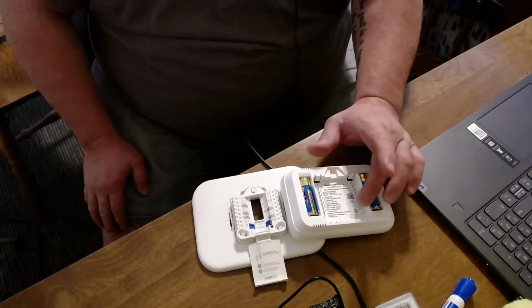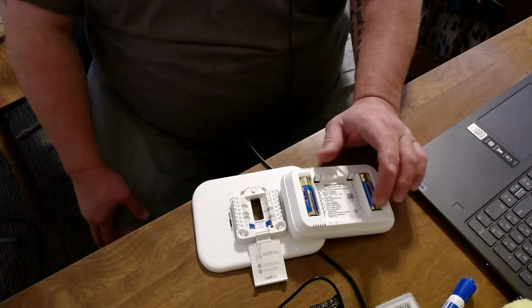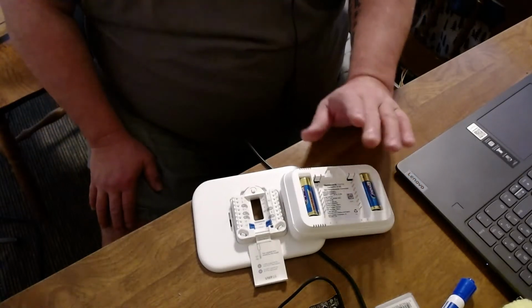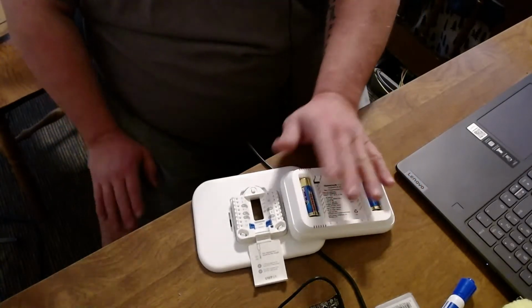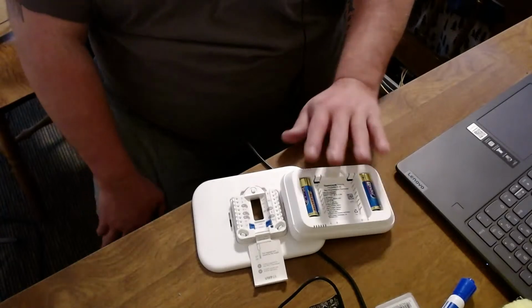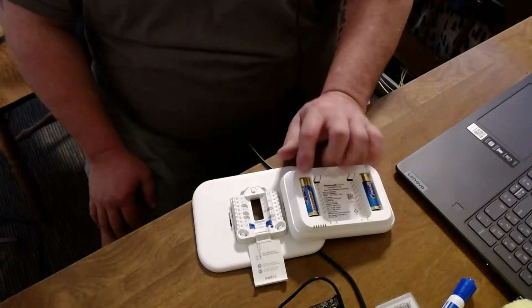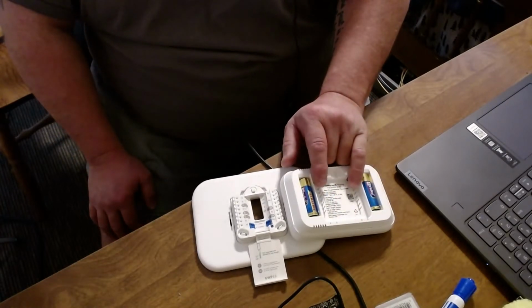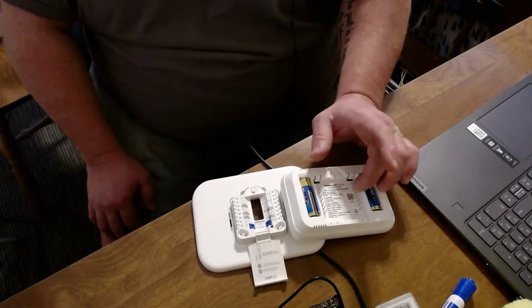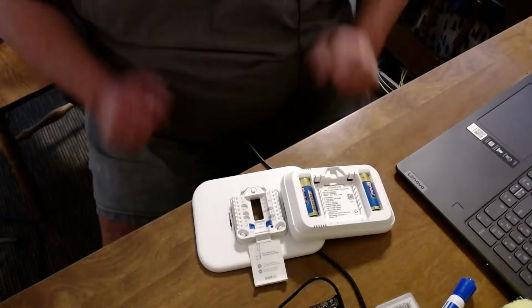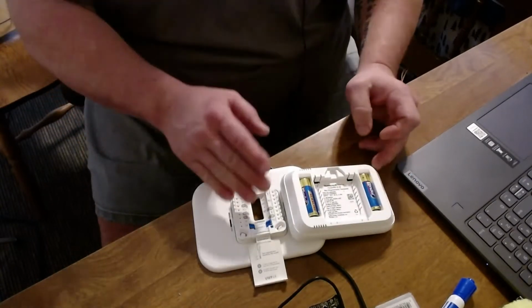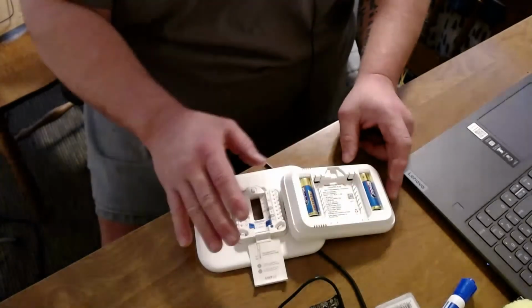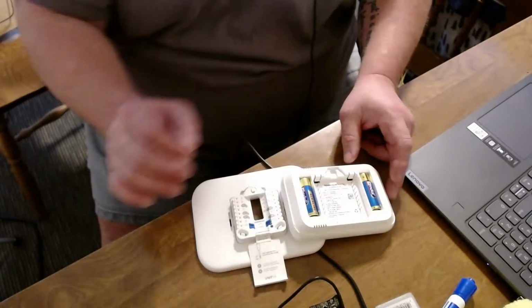You had the batteries, you could check the pins, and same with the old Focus Pros, you could check the pins. The new ones that don't have batteries, batteries are not required. I like the batteries so I can just energize the thermostat and see if I'm getting continuity through my pins to make sure they're working. And when we go over it on March 8th about diagnostics, we'll actually do that test.